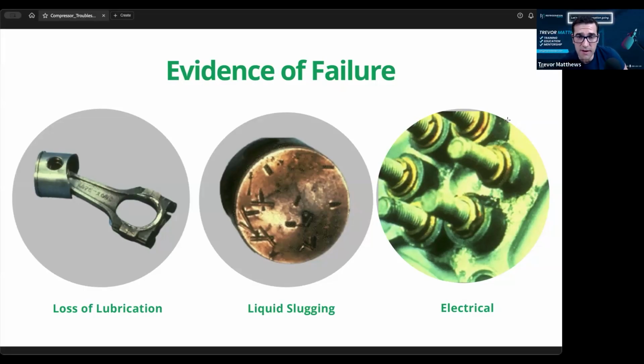You got to have a drip time after the defrost. So you go into the E2 or the Danfoss or Micro Thermo, and you set up your drip time. Follow manufacturer's instructions. It's all in there. It could be 5 minutes. It could be 10. It all depends. But you gotta look at that stuff. And these are just visual signs. This is before you even need tools out. You can go and take a look at that, and you say, "Oh man, we got something going on here. Let's check this evaporator coil," and then that affects what's going back to that compressor. Okay, great.